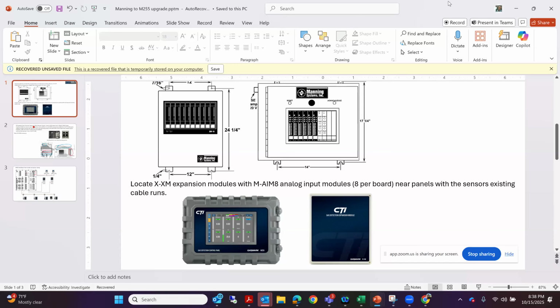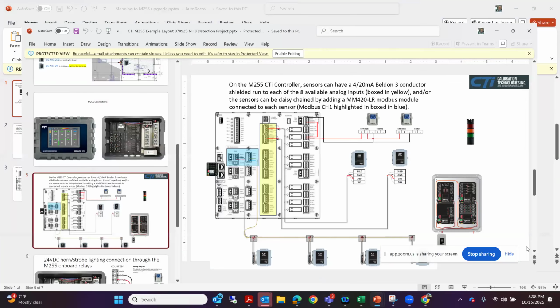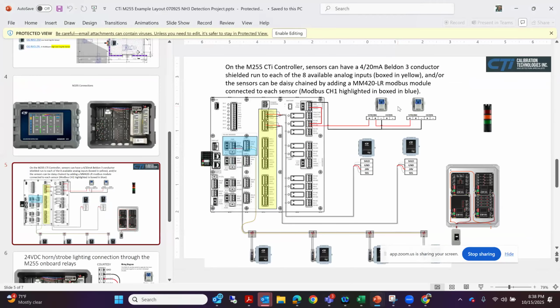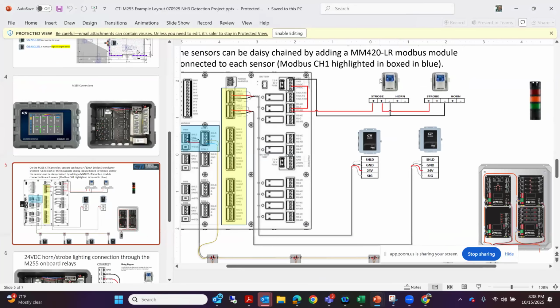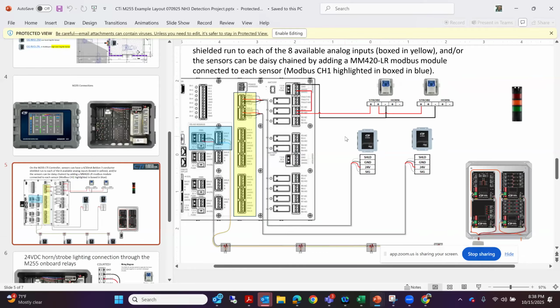And so if they're okay with it being 24 hours, then I'm okay with it being 24 hours as well. The problem with figuring out these UPSs on these systems is that, like we were talking about before, to really meet the horn strobe objective and get so many of these horn strobes out there. Yes, they might only draw 150 milliamps, so every 10 of them is 1.5 amps, which is not a big deal.